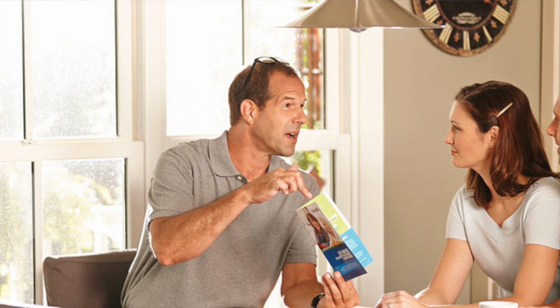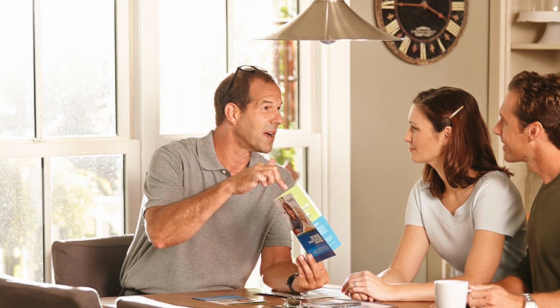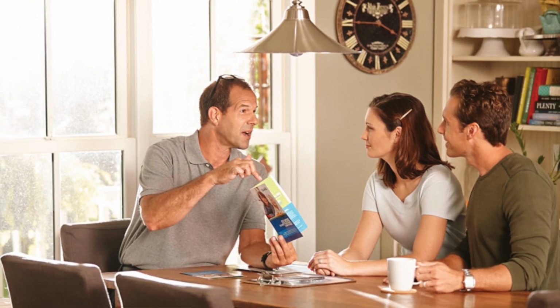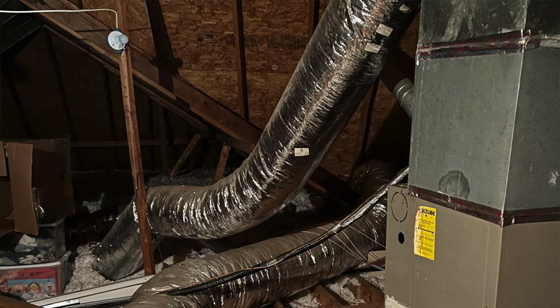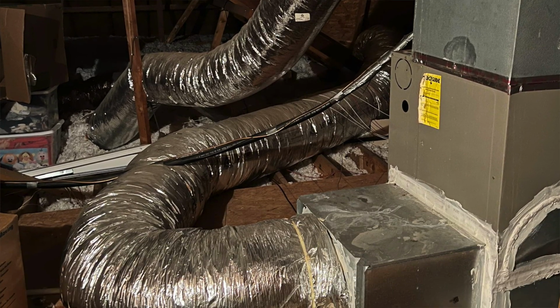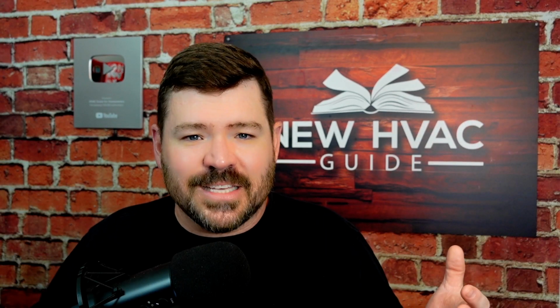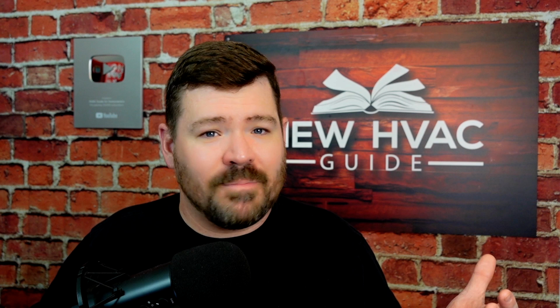I'm simply saying if the contractor didn't even look, if the salesperson didn't even walk around and look at all the vents and the ductwork and make sure that there's no big problems, then when you get to the end of the job and the installer's installed the system, now you're having these issues, because that's how it always happens. You find out after the fact that the salesperson, the first person that came to your house, should have done these things. They should have done a load calculation.